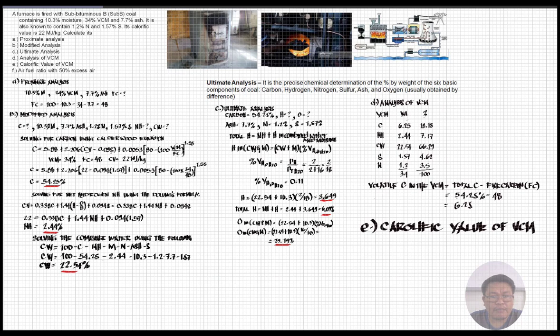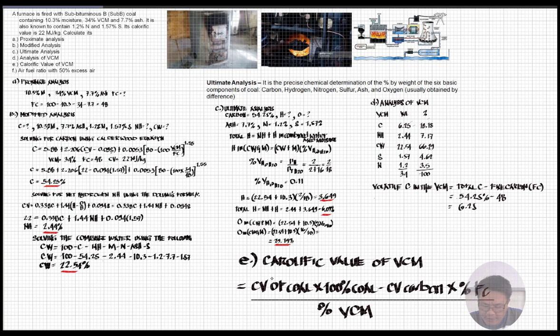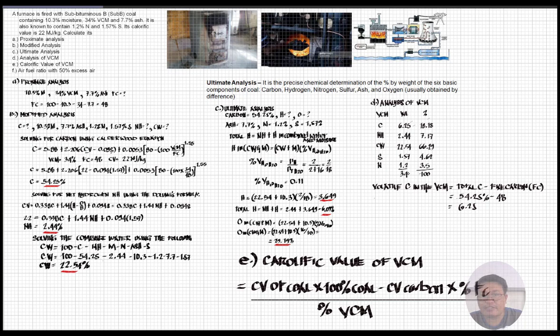For letter E, we need to determine the calorific value of the VCM. The equation is: calorific value of VCM equals the calorific value of coal times 100 percent of coal, minus the calorific value of carbon times the percentage of fixed carbon, all divided by the percentage of volatile combustible material. The VCM percentage total is 34, and the calorific value of coal is already given as 22.22 megajoules per kilogram.